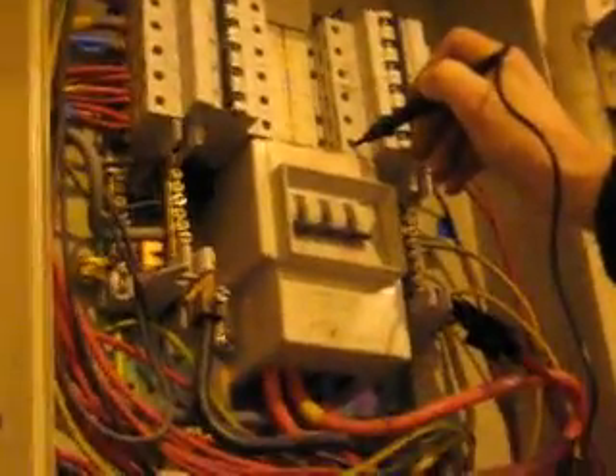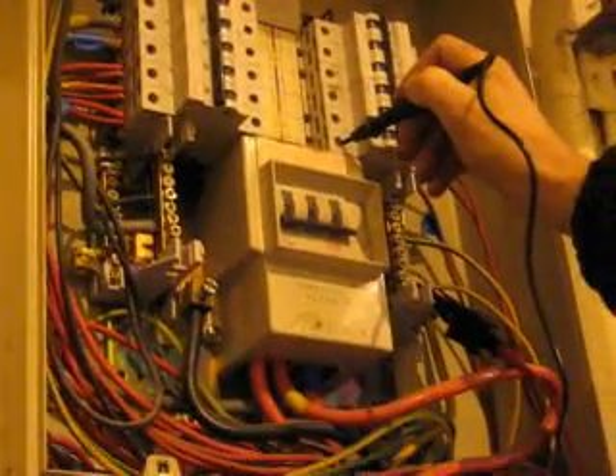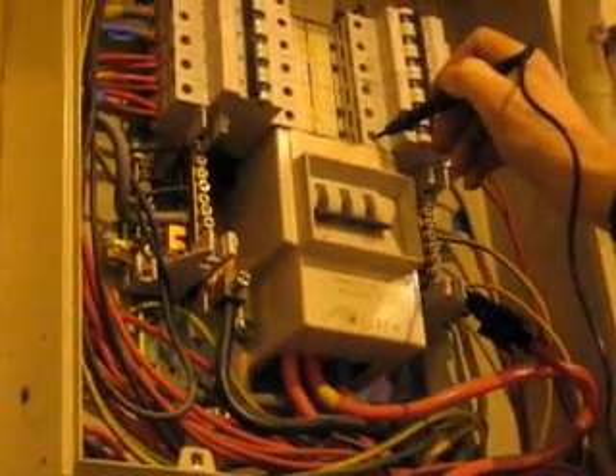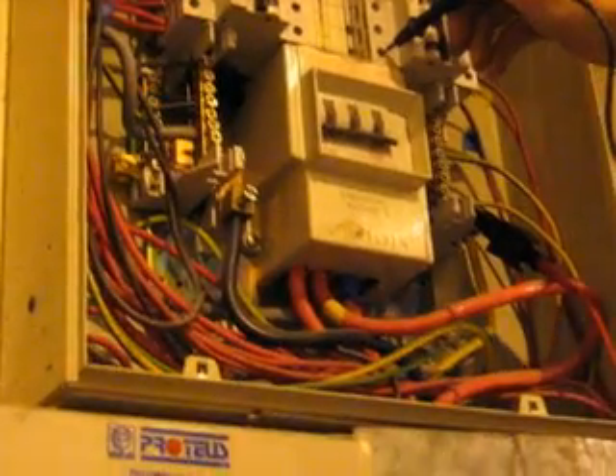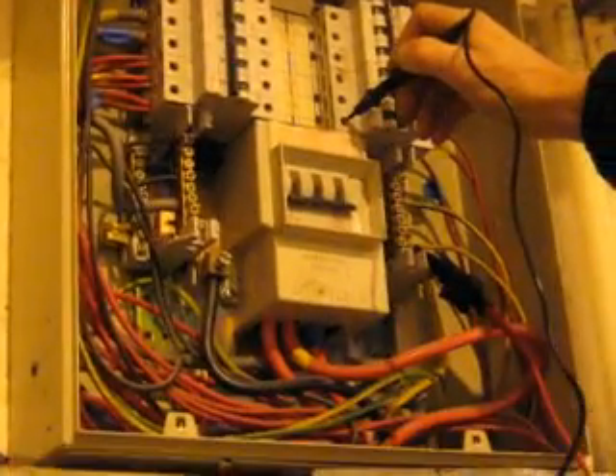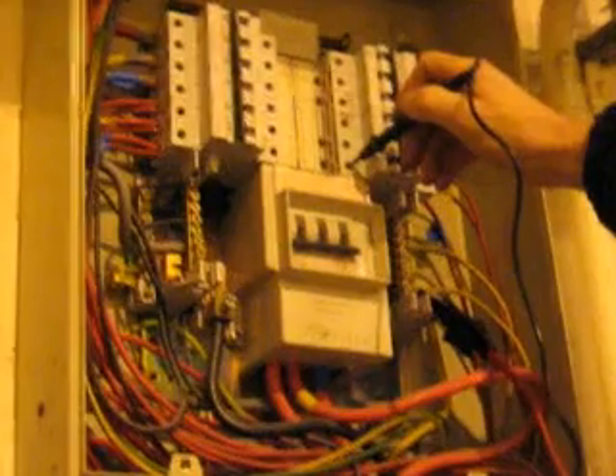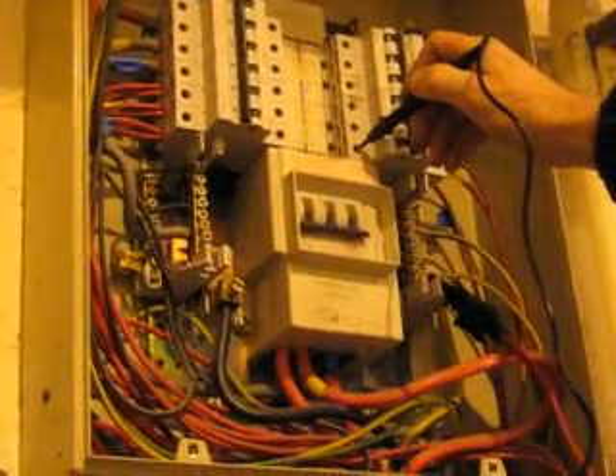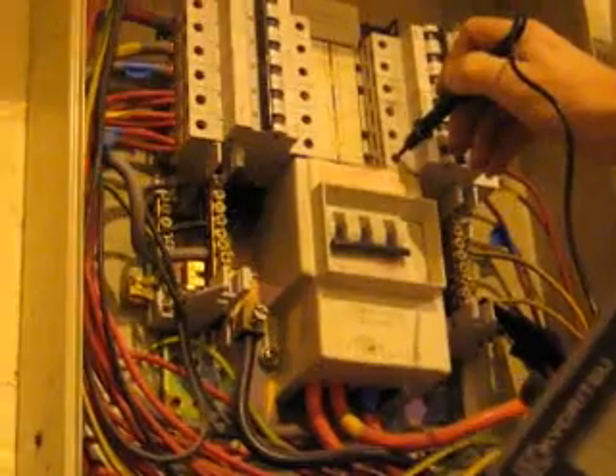This is a test of insulation resistance, and the test being conducted is a test between line 1 and earth. Prior to the test being conducted, it was necessary to release the neutral link that joins the incoming neutral to the distribution board. Without that link being removed, you would get false short circuits indicated on your instrument. The reading at the moment is out of range, which indicates it's greater than 200 megohms. This test would be repeated for all three phases.